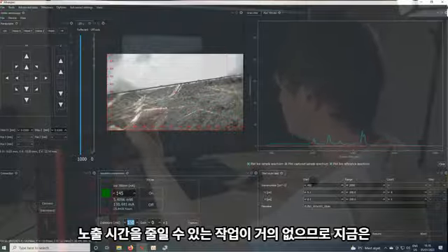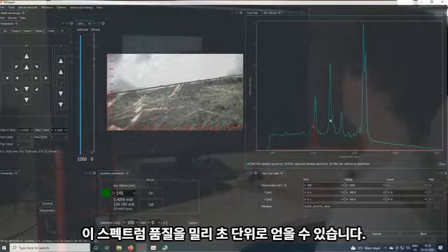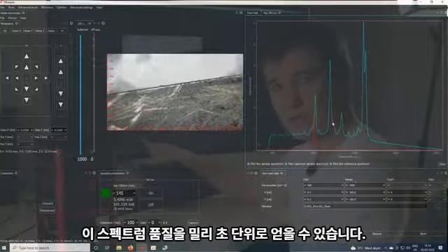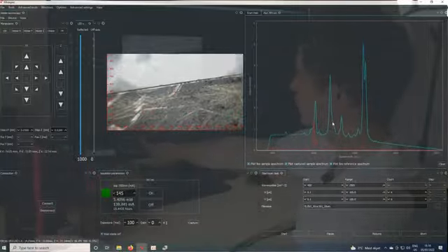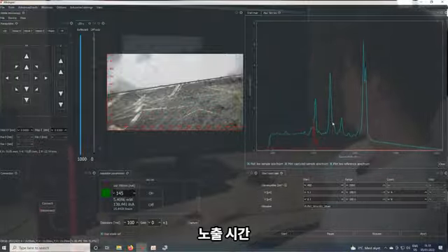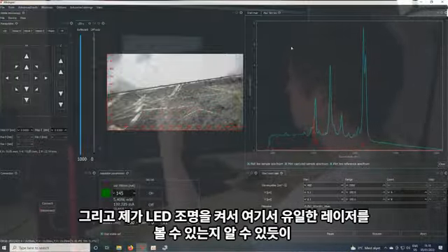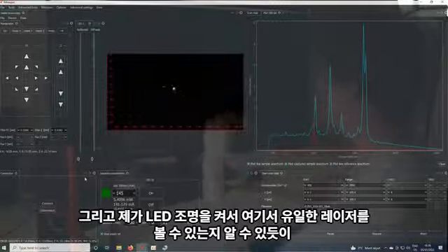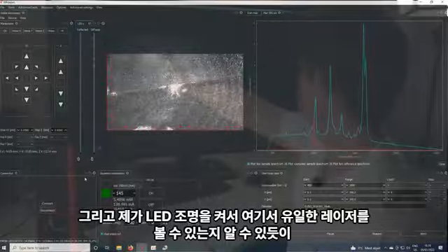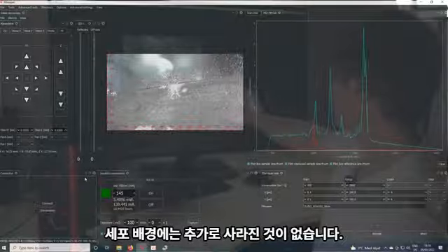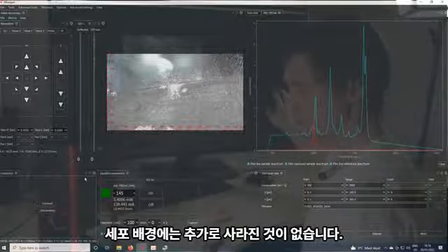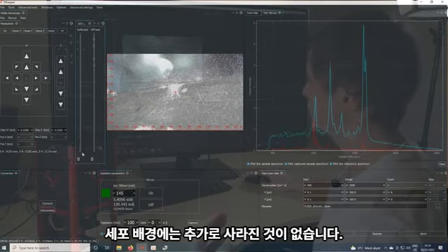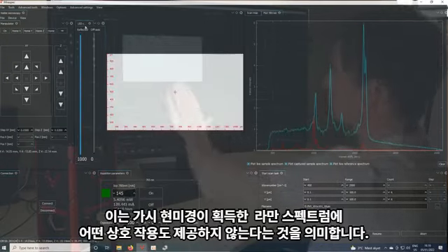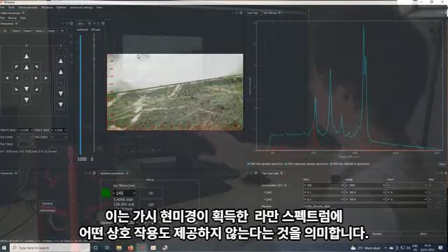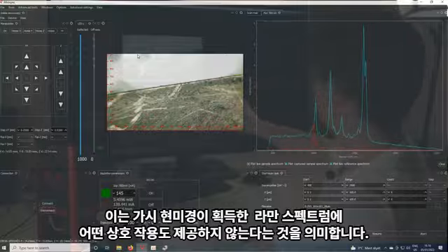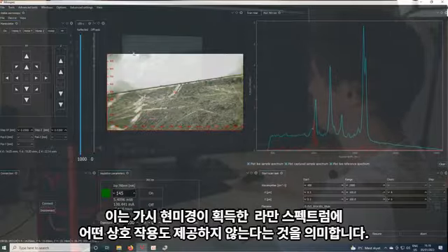So right now, this quality of the spectra we get only at 100 milliseconds of the exposure time. And as you can see, even if I turn on the LED light, so we can see only the laser here, nothing extra appears in the SERS background, which means that visible microscopy does not provide any interaction to the Raman spectrum acquired.